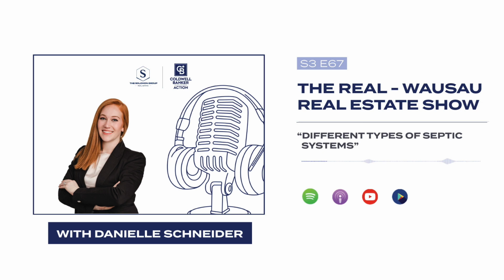Similar to the conventional system, the mound collects all of the wastewater from your home, where the solid material settles to the bottom of the tank and the liquid material is filtered and slowly dispersed throughout the layers of material found within the mound. Unlike a conventional or a holding tank system that is buried underground, a mound system sits above the ground and requires a pretty substantial amount of space. Maintenance of a mound system is similar to that of a conventional, where the state requires inspection every 3 years. Pumping frequency, again, depends on the amount of wastewater produced.